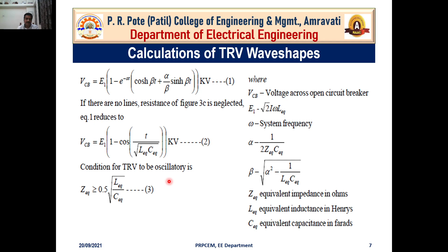Now what is the condition for this TRV to be oscillatory? The equivalent impedance should be greater than or equal to 0.5 times the square root of L equivalent divided by C equivalent. This is the condition for TRV to be oscillatory in nature, and that way you can obtain this one-cosine waveform. So this is a small derivation of how we can find the TRV wave shape by considering the system.